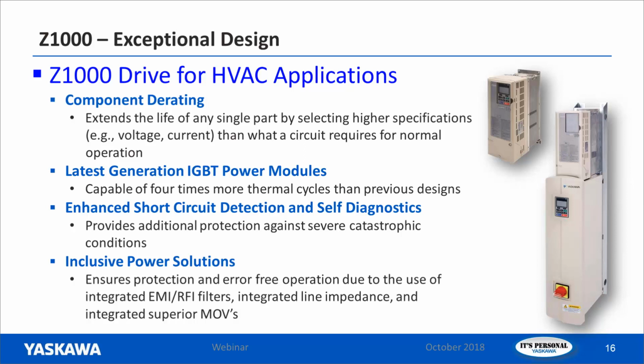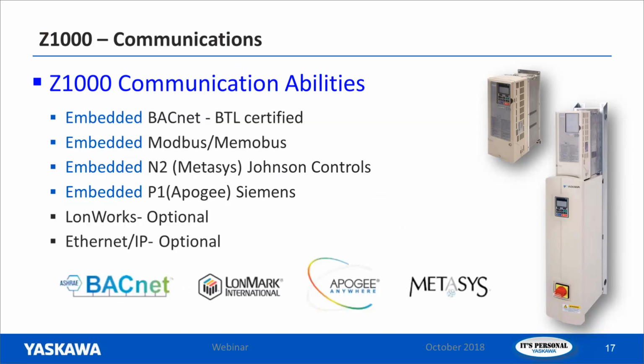And of course, inclusive power solutions. That includes our EMI RFI filter on the input, and as I mentioned earlier, our built-in 5% DC bus impedance. We also use superior MOVs for surge protection on the input. The communications I mentioned earlier, we have the 4 embeddeds, which are BACnet, Modbus, N2, and Apogee, but we also have the ability to add an option card for LonWorks or Ethernet IP.